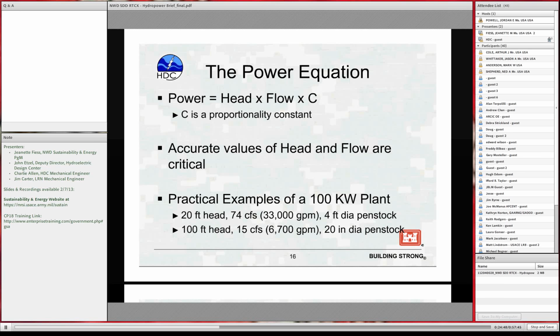If we jump to, say, increase the head by a factor of 5, go to a 100-foot head site where the elevation drop of the water is 100 feet, then you decrease your flow by a factor of 5. So we're down to 15 CFS, 6,700 GPM. And in order to deliver that water to the machinery at a reasonable rate, you need about a 20-inch diameter penstock or a 20-inch diameter feed pipe. One of the interesting things here is that the physical size of the turbine that produces this energy is approximately proportional to the size of the penstock or the pipe that feeds it. So you see that as we increase the head, the size of the equipment, the size of the infrastructure, everything else decreases proportionately for the same power output.